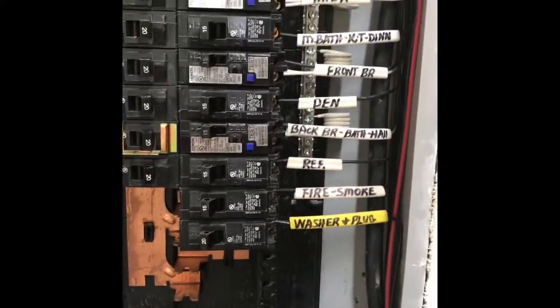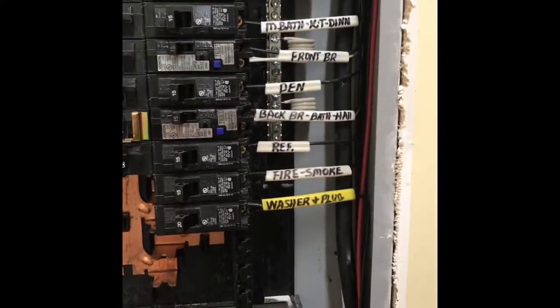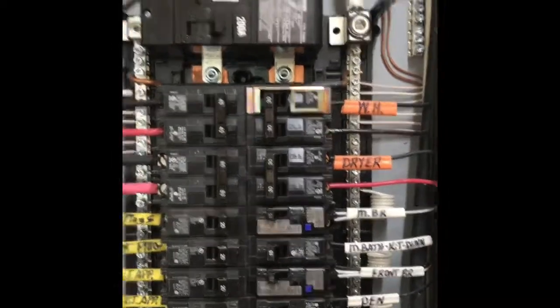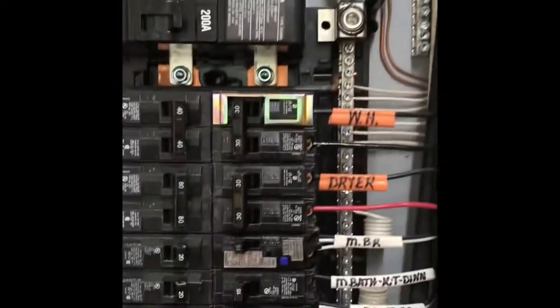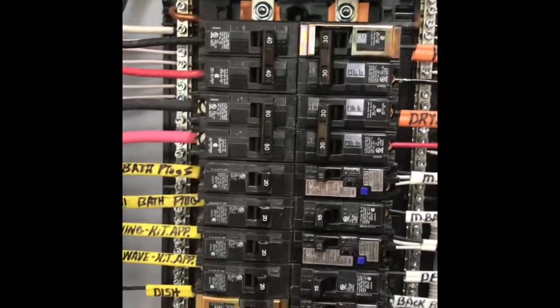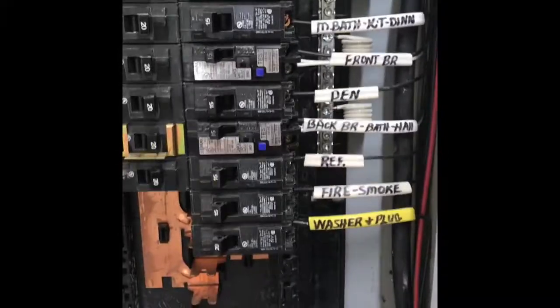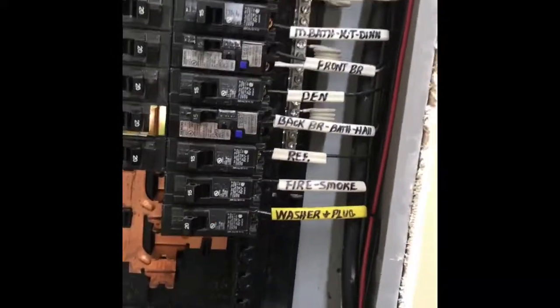A lot of times in Tennessee, you'll see the electric meter all the way on one side of the house and the panel on the other. When they do that, there'll be a disconnect at the main meter right underneath it, usually just a single 200 amp disconnect. That's considered actually the main panel. And then they'll run the service line through the crawl space or in the slab to wherever they're going to put the electrical panel in.